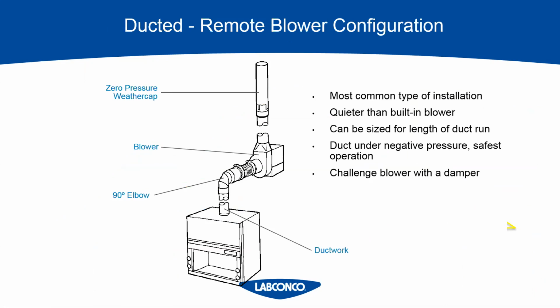So this is the most common type of duct layout, starting out with ducted. It's a remote blower configuration. In this image, starting with the hood at the bottom and moving up, we have the ductwork connection on top of the hood. Then we have a 90-degree elbow, since the inlet to the fan is actually on the side of the fan. That's why we have to have at least one 90-degree turn. Then we have the remote blower that's located most often on the rooftop or in an attic space, basically some unoccupied interstitial space that has enough ventilation for that blower. And then we have a vertical outlet that has a zero pressure weather cap as the termination, like what you see here.